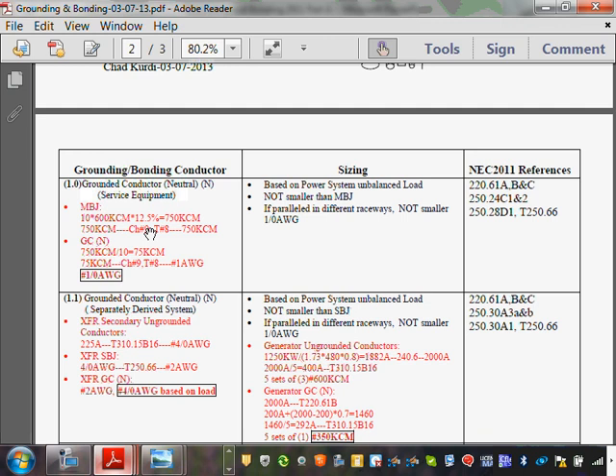Then you take that number, guys, and you divide it by 10. Why did I divide it by 10? Because there's 10 grounded conductors, one in each conduit. That gives you 75 kcm, well, 75 translates to number 1. And I'm paralleling. Can I pull number 1 if I'm paralleling? No. So what do you need to do? The minimum. Why not? That's where the 1/0 came to be. So with the system, I say minimum.